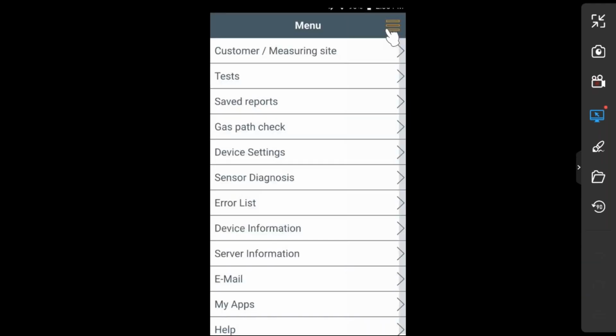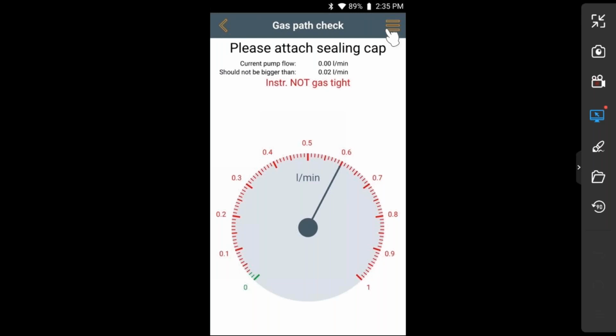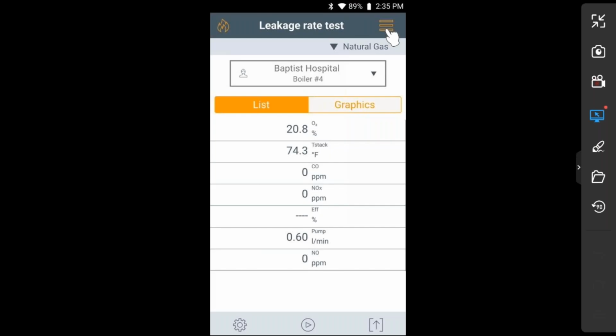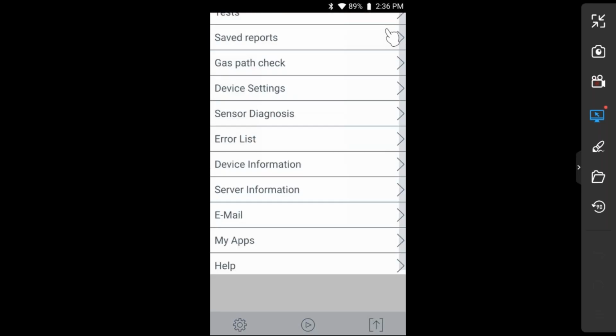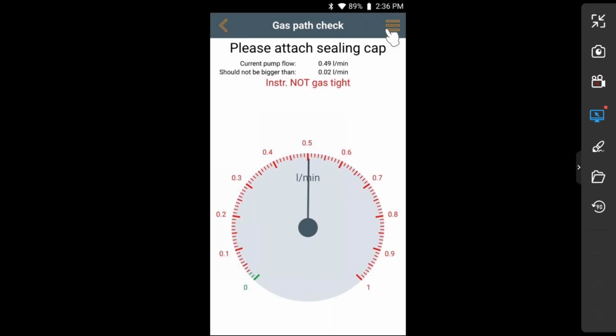One of the things I wanted to show you was gas path. This is a pretty important test, I think. You should do this about once a month on a combustion analyzer. What we're doing is looking at the path of the gases through the probe and hose assembly. With your analyzer, you get a rubber cap that goes on the tip of your probe. Here it's telling me my liters per minute. If I put that rubber cap on the probe tube of my probe and hose assembly, I'm going to create a vacuum in my instrument.